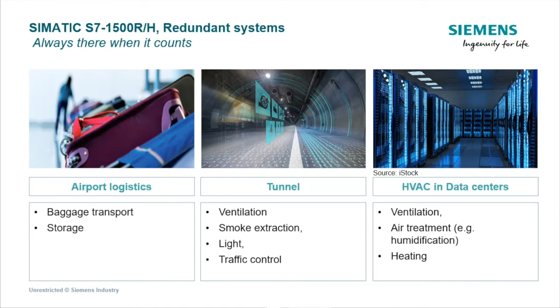So if you must update a CPU, or you have a failure, you do not want these processes to stop. It's worth a lot of time and money, and it's worth paying a little extra for the CPU to ensure that, in worst case scenarios, if a controller dies, you will have a controller on backup ready to take over that control program.